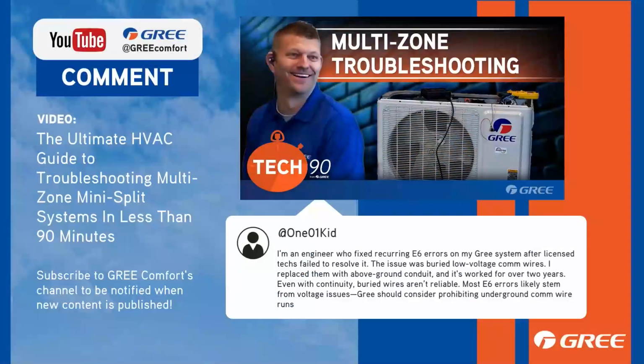I'm an engineer who fixed recurring E6 errors on my GREE system after licensed techs failed to resolve it. The issue was buried low voltage comm wires. I replaced them with above ground conduit and it's worked for over 2 years. Even with continuity, buried wires aren't reliable. Most E6 errors likely stem from voltage issues. GREE should consider prohibiting underground comm wire runs.